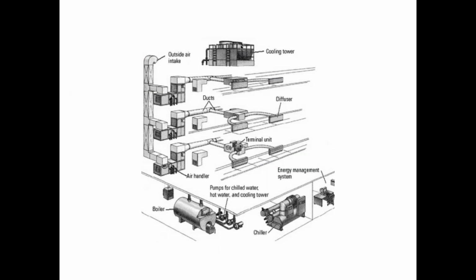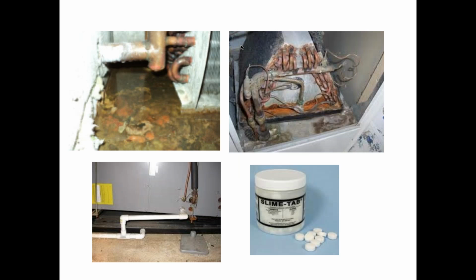Now, when we look inside these air handlers, one of the things that we do in an indoor air quality survey is we'll look, Mike will go in there and say, let me take a look inside your air handler. Well, why do we want to take a look inside the air handler? We want to see if the filters are in good shape. We want to see if the coils are clean. We want to see if there's mold growing. We want to see if the condensate's draining properly. Is there slime growing in there? What's the inside of this air handler look like? Is it sanitary? Right, here's a couple of pictures of condensate pans in a typical air handler.